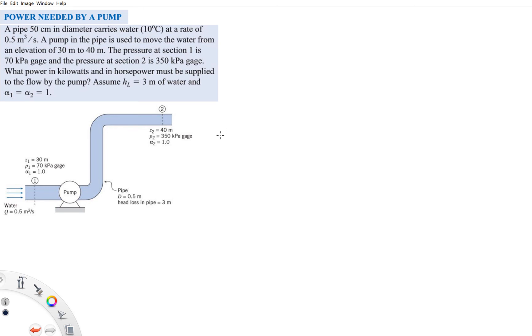In this example we have a pump that carries water from a lower to a higher elevation. The pipe before and after the pump has the same diameter of 50 centimeters, and it carries water at 10 degrees Celsius at a flow rate (discharge) of 0.5 cubic meters per second. The pump moves water from 30 meters to 40 meters elevation. The pressure at section 1 is 70 kPa gauge and at section 2 is 350 kPa gauge. We need to calculate the power input in kilowatts and horsepower.